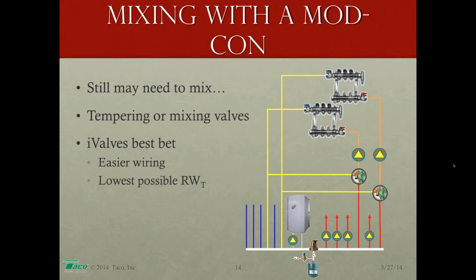a loop system, primary, secondary, like on a cast iron boiler. You always take the highest temperature ones off first and the lowest ones off last. In this type of a piping arrangement, a moose antler piping arrangement, it is my belief that it's not as critical. Okay, it's because we're not doing any mixing on the primary.